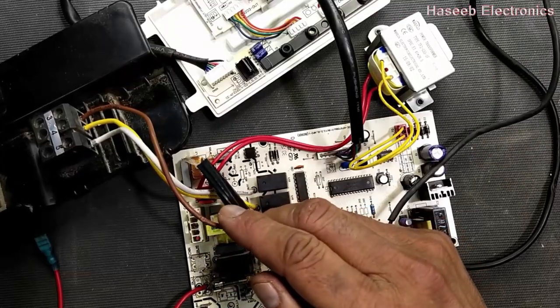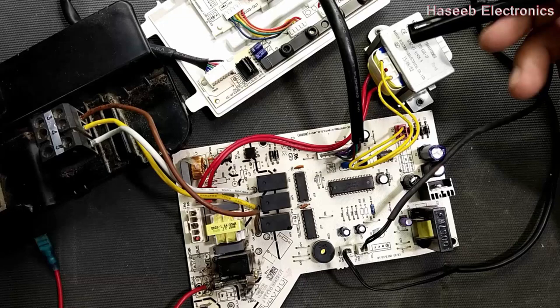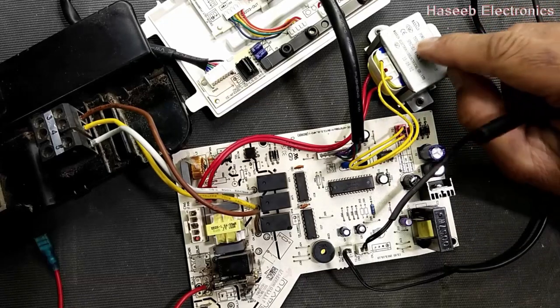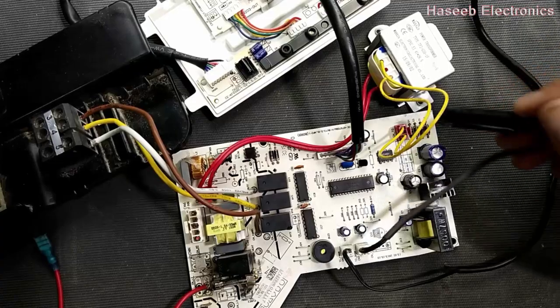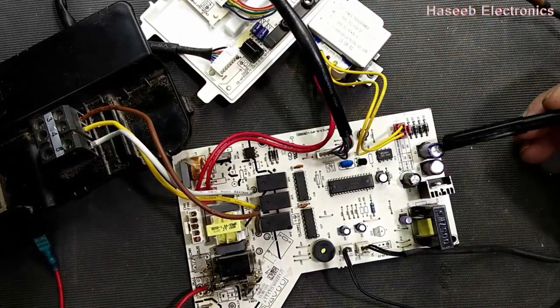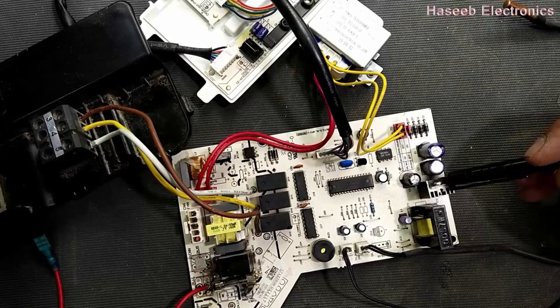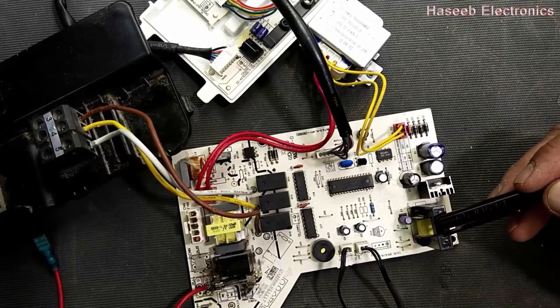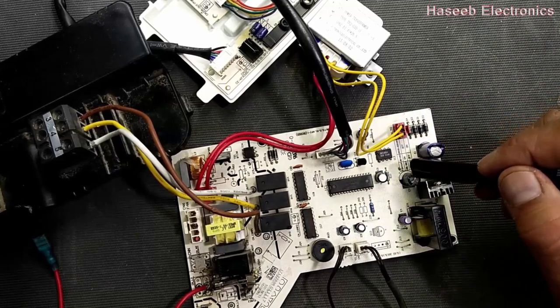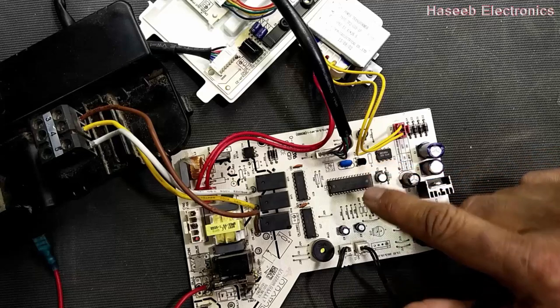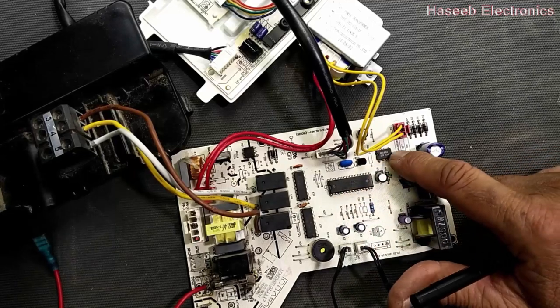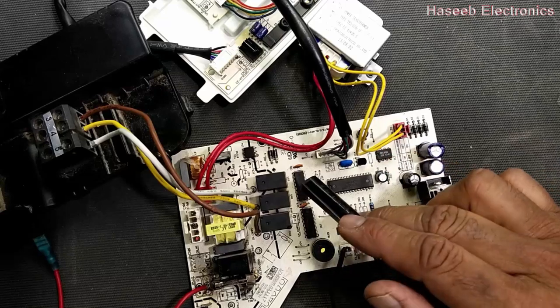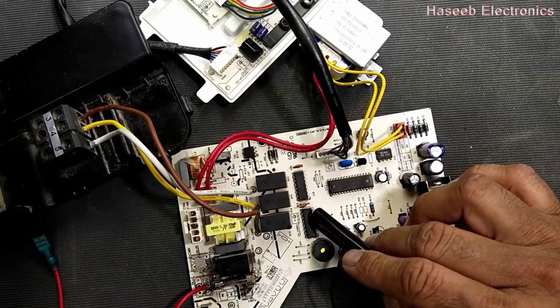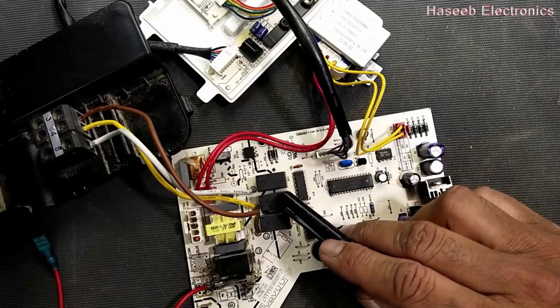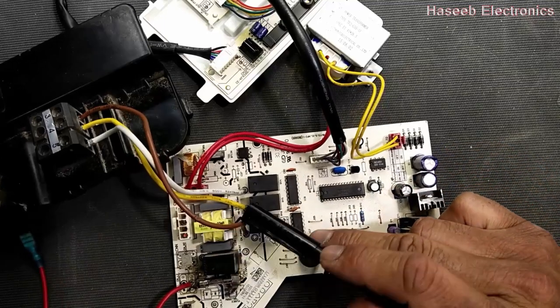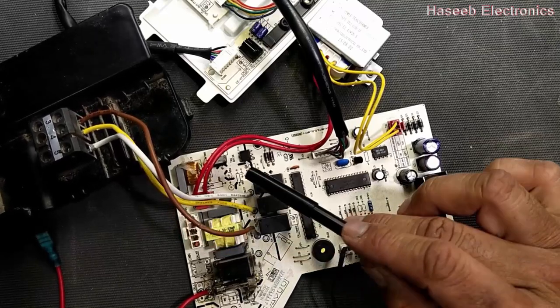Power input, transformer. From the transformer 220 volt, we take the output voltage here, isolated voltage. We have a bridge rectifier here, 4 diodes, then a capacitor, then a voltage regulator. Here we have a current transducer, which checks the amount of current. Then we have a 5 volt regulator, the microcontroller, a serial EEPROM, and ULN2003 ICs, which are Darlington BJT arrays. We have 3 relays: compressor, heat and cool valve, and outdoor fan.